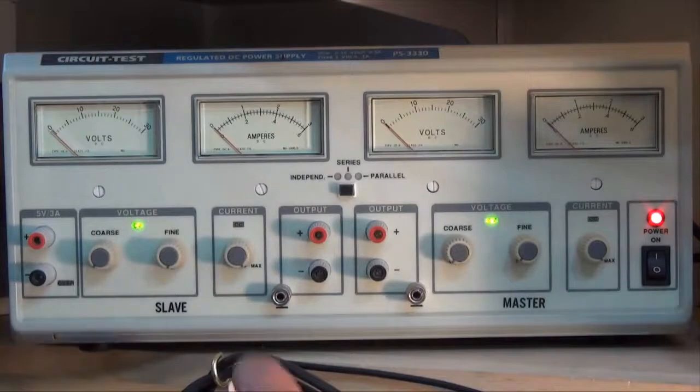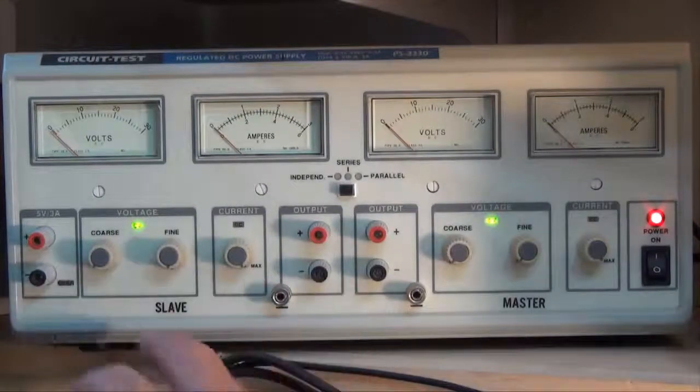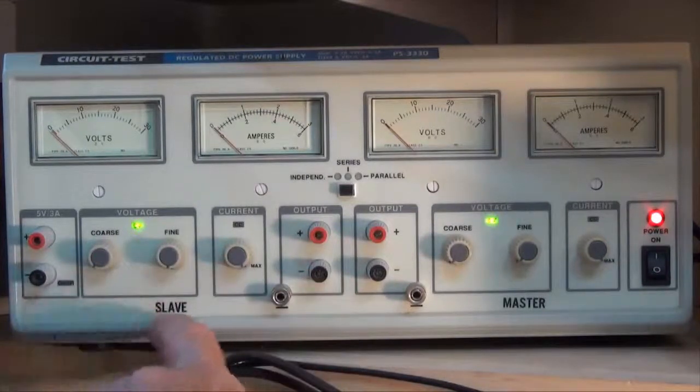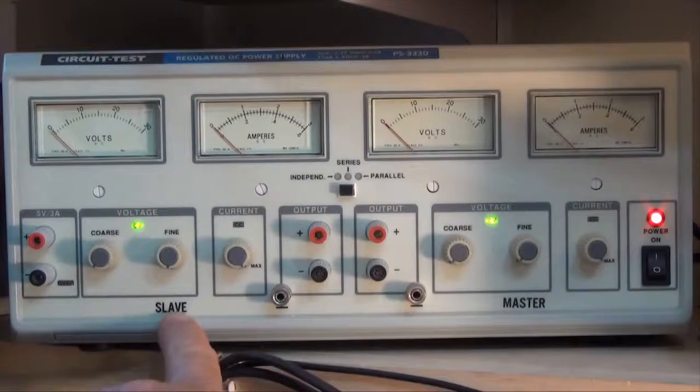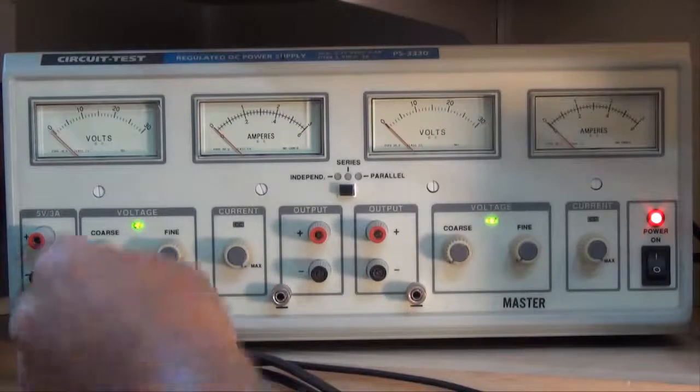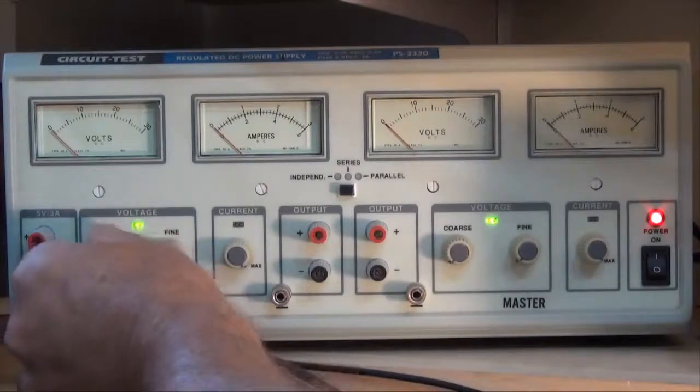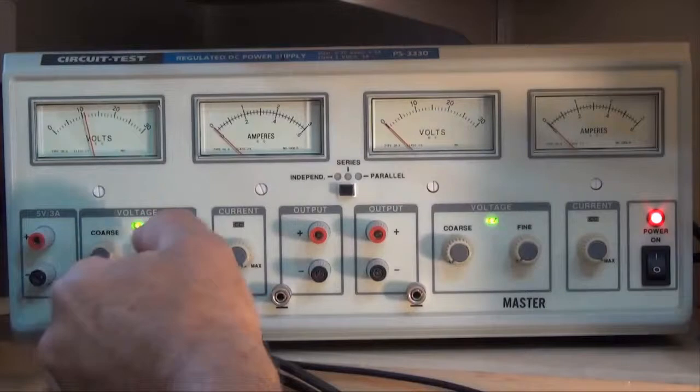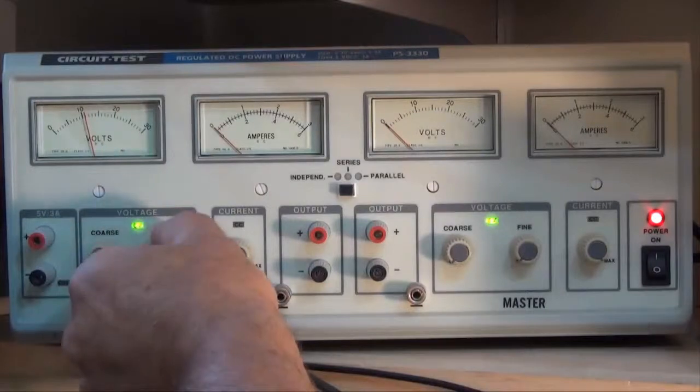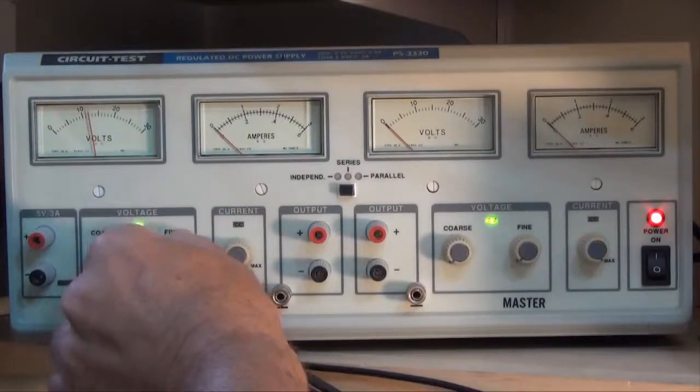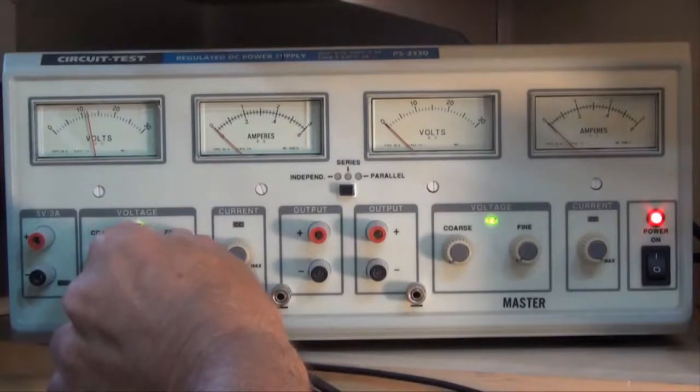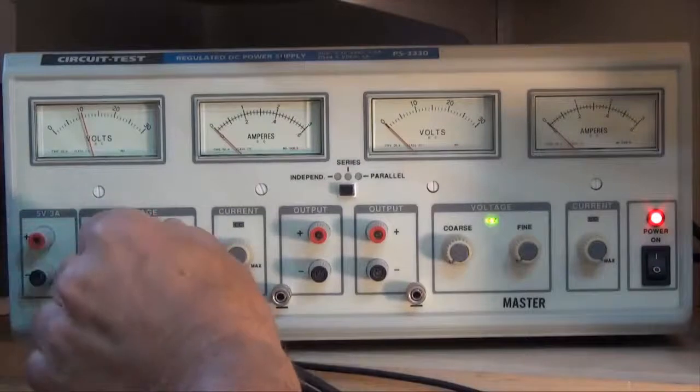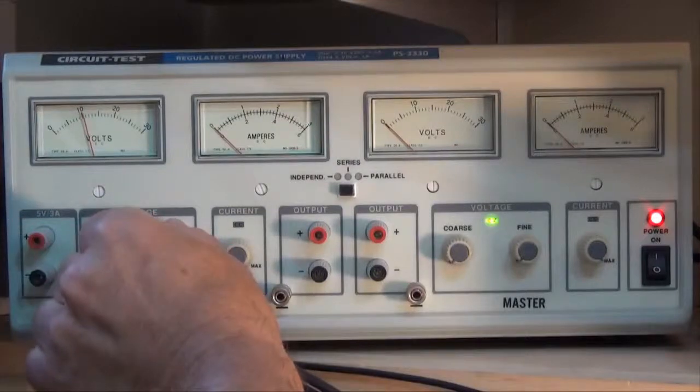To adjust the voltage on the left side or under what's called the slave side, I use the coarse voltage control. And then if I want to fine tune it, I can use the fine control. So we can set this roughly to 10 volts. There we go.